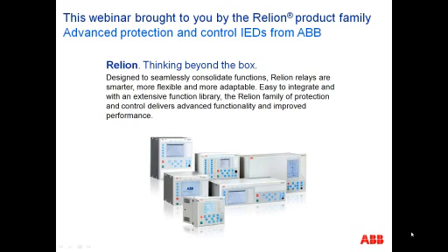All right, but where a problem might occur with a PUTT scheme is that if the remote breaker is open, it can't detect the line fault beyond the setting of the zone 1. POTT addresses that because you're using an overreaching zone to send permission, and likewise you have to receive permission and you trip with an overreaching zone. I hope that clears it up. Elmo, the TT part of POTT and PUTT, TT stands for? Transfer trip. Transfer trip. Okay.